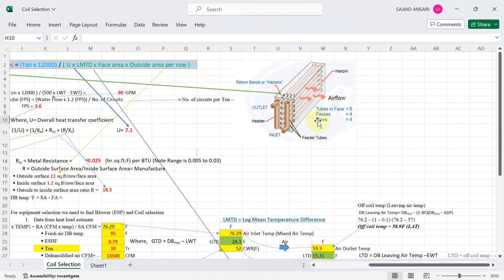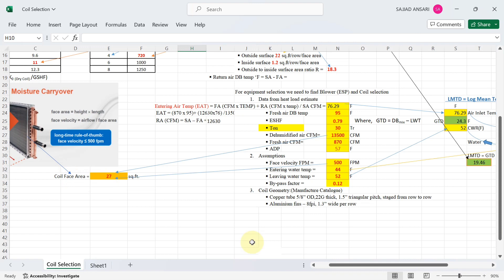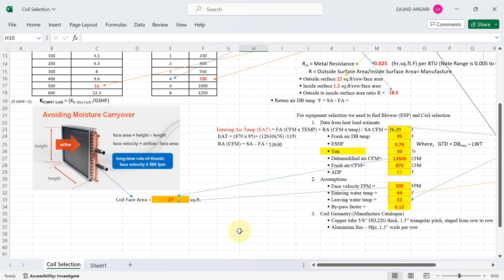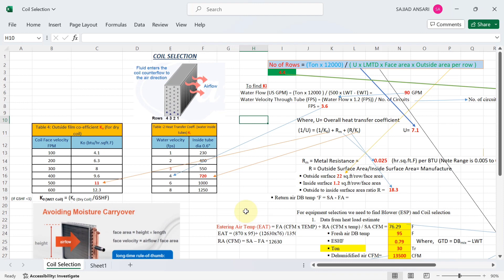So we round to 4 number of rows for our coil — one, two, three, four. In this way we calculate the number of rows and face area. We submit these to the manufacturer along with the dehumidify CFM value. Total air CFM is also required: dehumidify CFM plus 12% of dehumidify CFM. These are all the details to submit to the manufacturer for coil selection. I hope you enjoyed this session — see you in the next one.